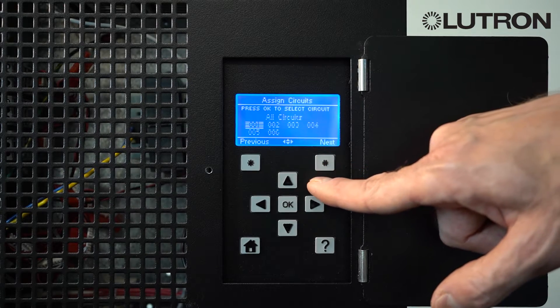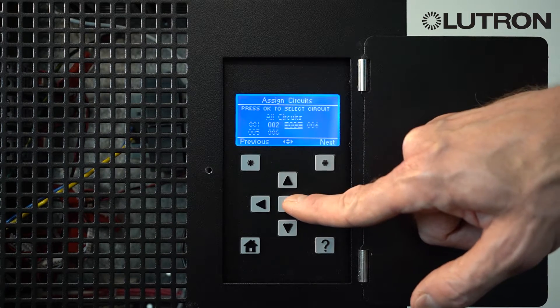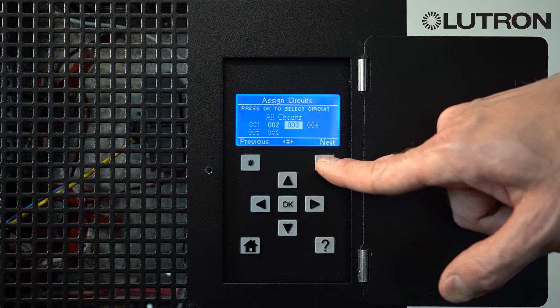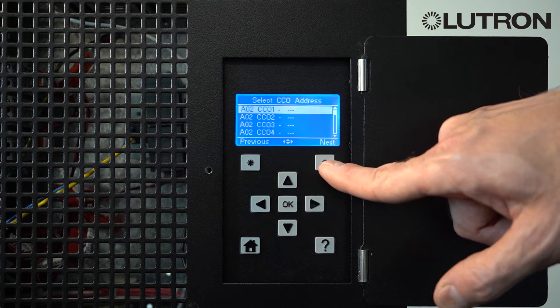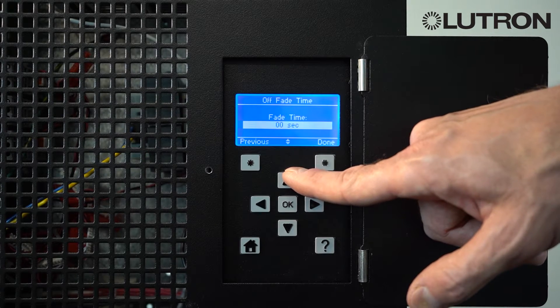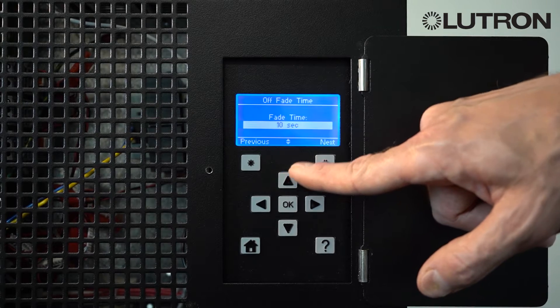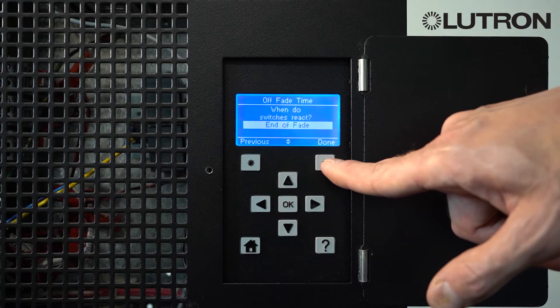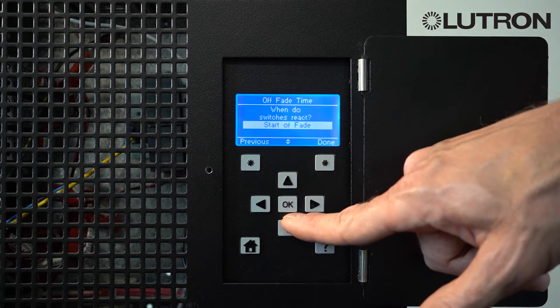Select Next, then select the zones you want to be affected. If you want zones 2 and 3, go to those zones and press OK to toggle them on or off. Select Next again. You can choose whether you want contact closures to be affected. Then choose whether you want any fade time associated with it — if there are dimmer lights in the space, it's generally a good idea to have a 10-second or more fade time to indicate to users that the lights are about to turn off if the sensor does not detect them. You can also select how you want switching zones to behave: at the end of the fade or at the beginning of the fade.